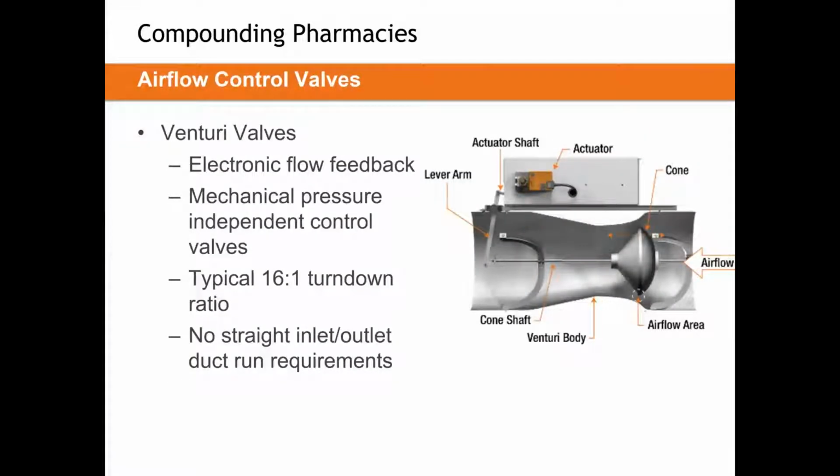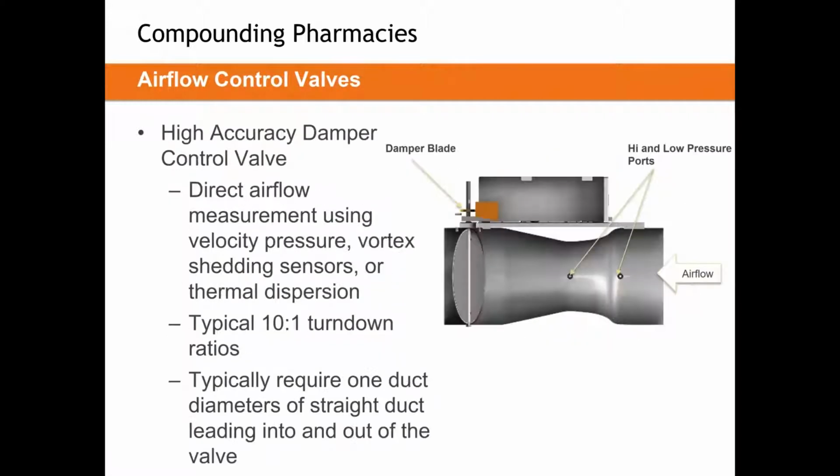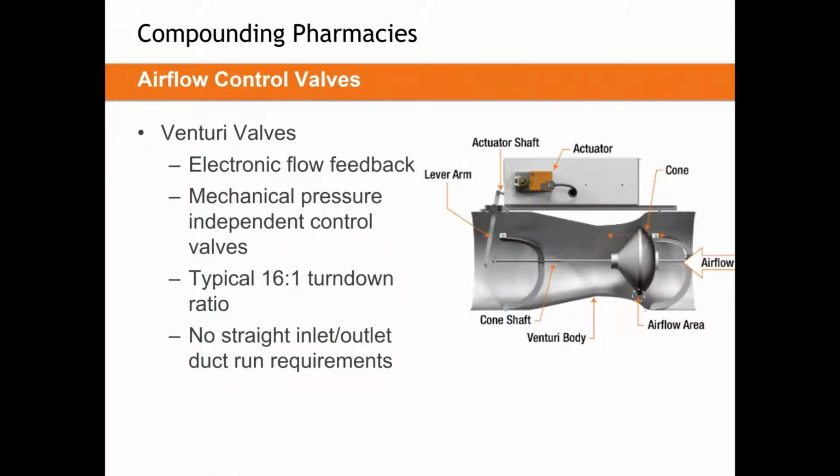The next one, and I like to draw a line in the sand here between high accuracy terminals and standard VAV boxes. I like to draw a line in the sand between that and Venturi valves. Sometimes these devices look the same. I'm going to jump back one slide. Sometimes high accuracy terminals and Venturi valves look nearly identical. But these technologies are extremely different. They are not identical technologies.